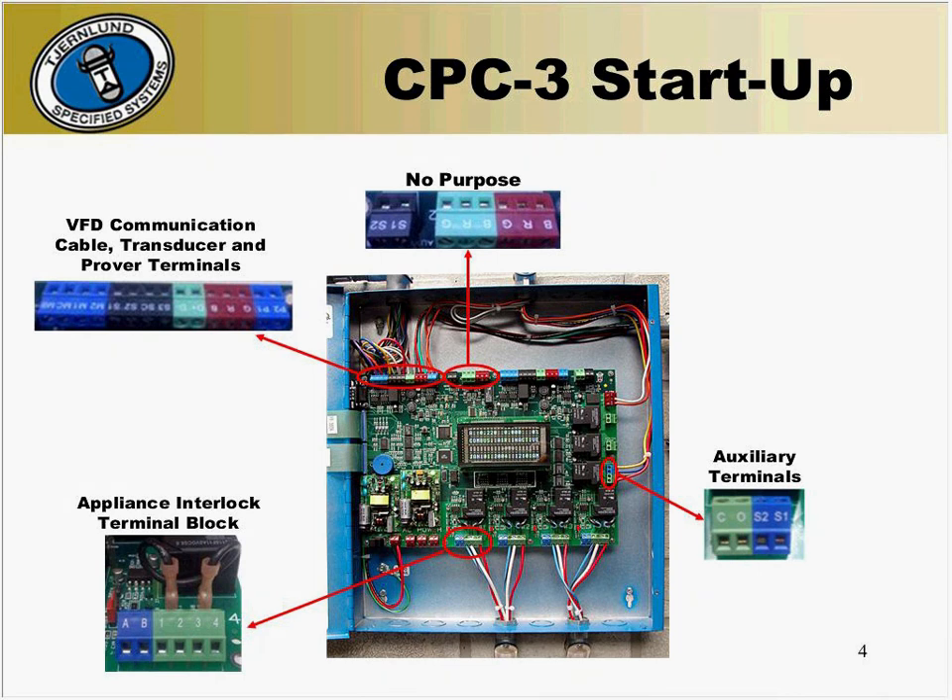Check the interlocking terminal blocks across the bottom of the panel. Verify there is a call signal on either A and B or terminals 1 and 2, and a run signal across terminals 3 and 4 or just terminal 4. You should also be checking for the 10-wire communication cable across the top of the board. Each terminal is color-coded with its corresponding terminal on the VFD block. If there are any louvers or CO detectors connected to the CPC-3, verify that the wiring on the auxiliary terminals at the lower right-hand side of the panel are connected. If there are any expansion modules connected, verify they are plugged in tightly and that all interlocking terminal blocks are wired properly.